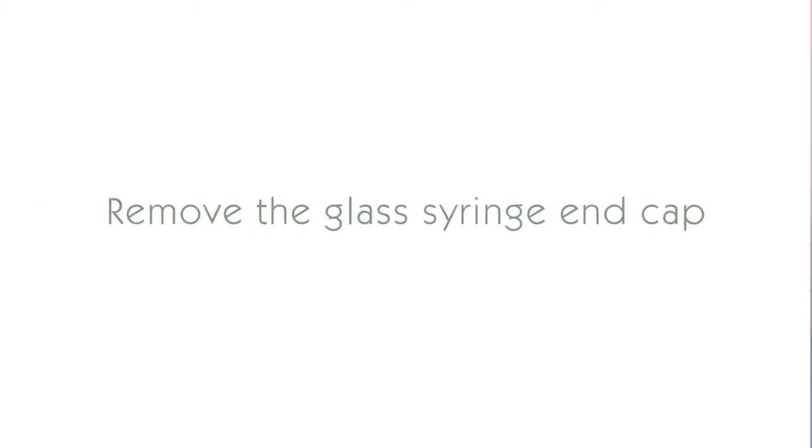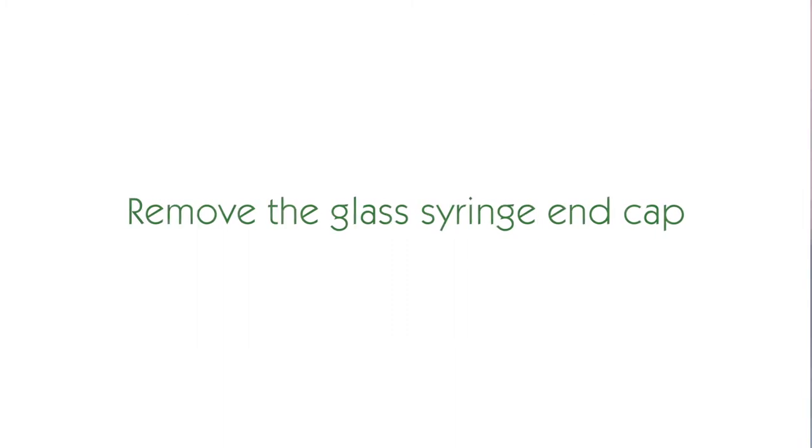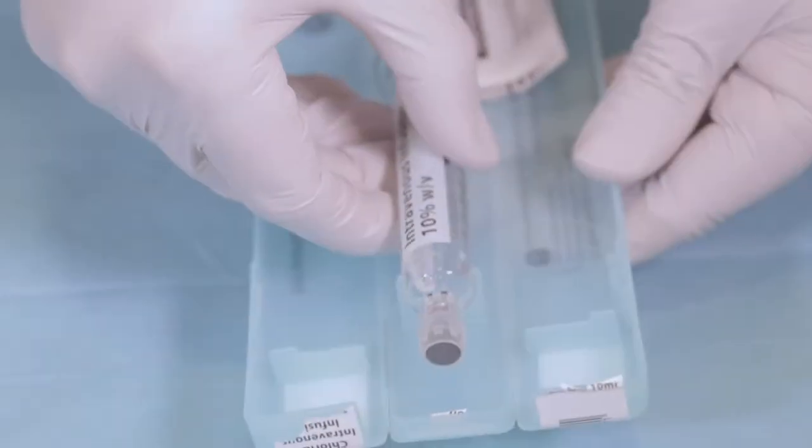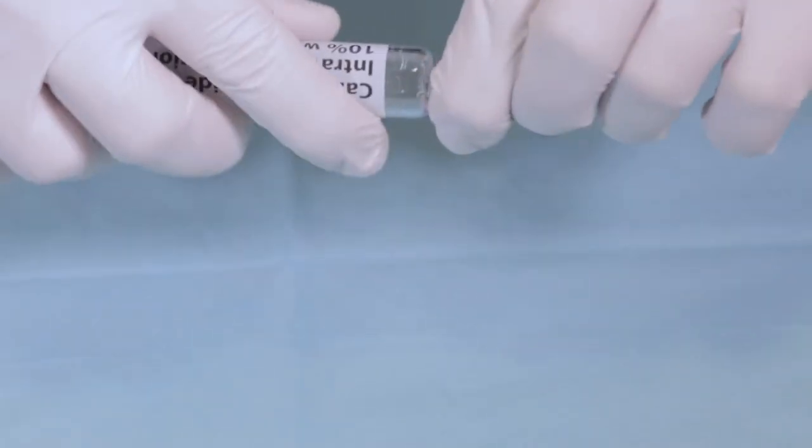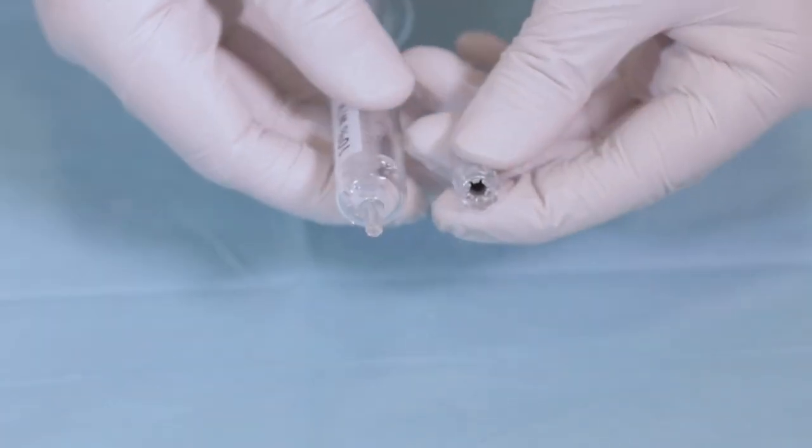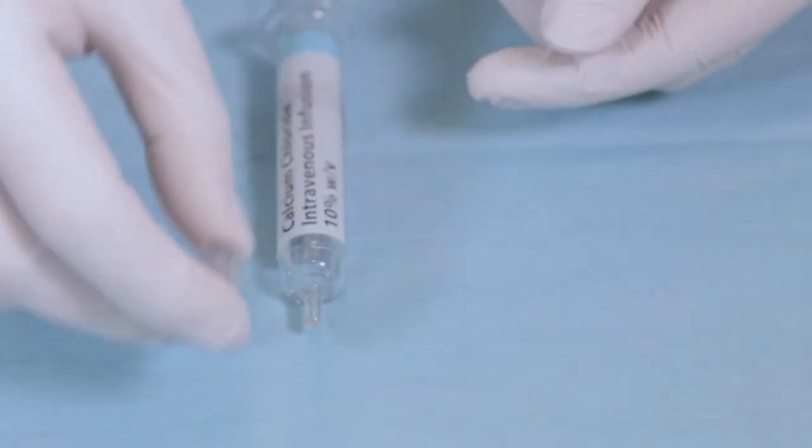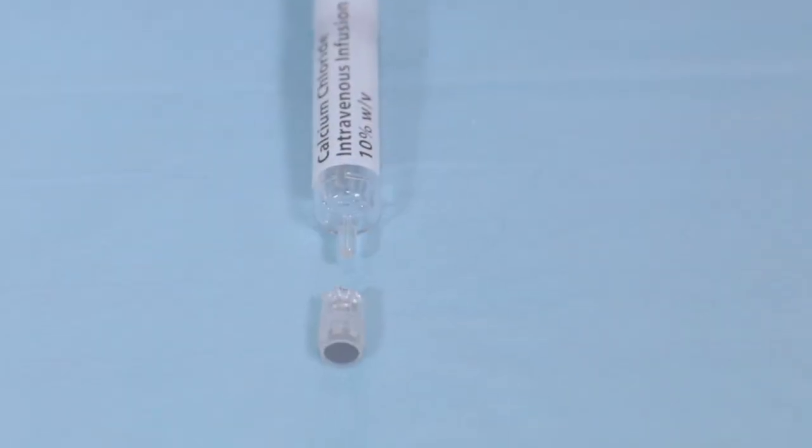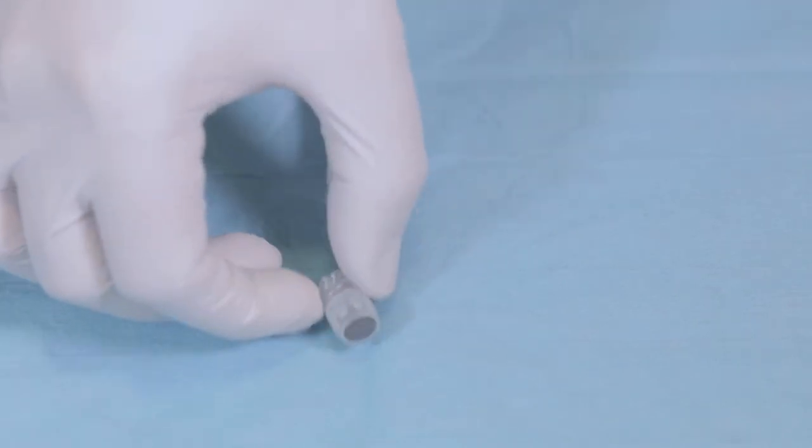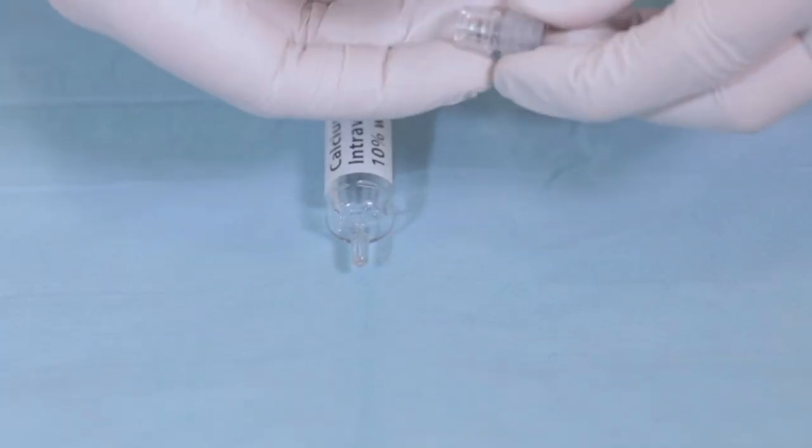Step 2. Remove the glass syringe end cap. Unscrew the syringe end cap from the Luer lock syringe or pull off the protector from the Luer slip syringe. Be sure not to accidentally remove the Luer locking collar from the Luer locking syringe.